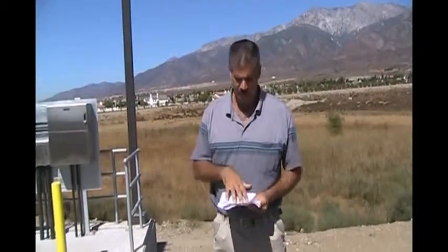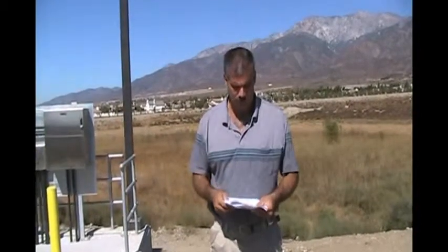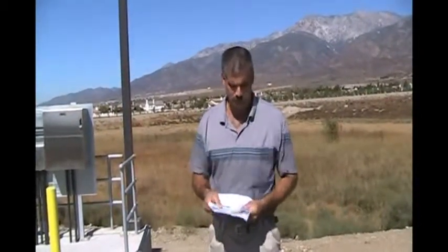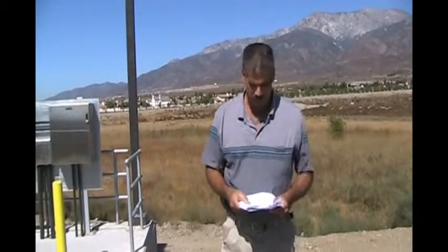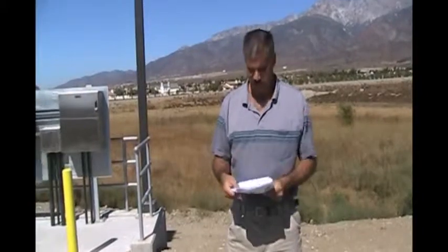On this screen right here, we have the ability to set all our low lows, low high, and high set points for our different basins. You'll see 1, 2, 3, and 5 on the bottom there. You also see the level offset, and that's where that can be set. It can be set local and or from the SCADA, so that's completely programmable. There's no apply button here either because nothing's going to act on it. If you put in the wrong value, you'll just be able to change it. It's not a big deal at this point.